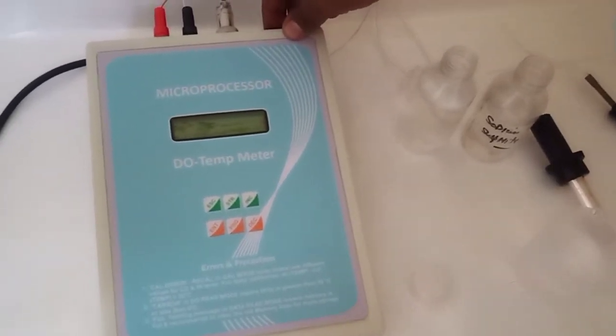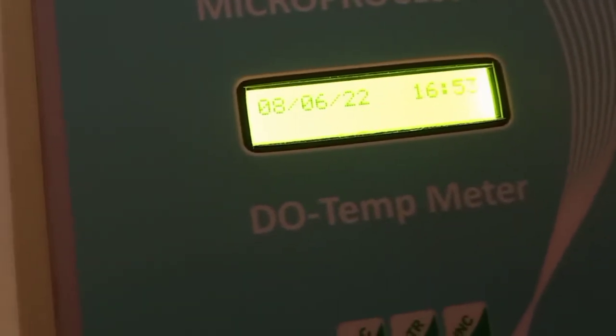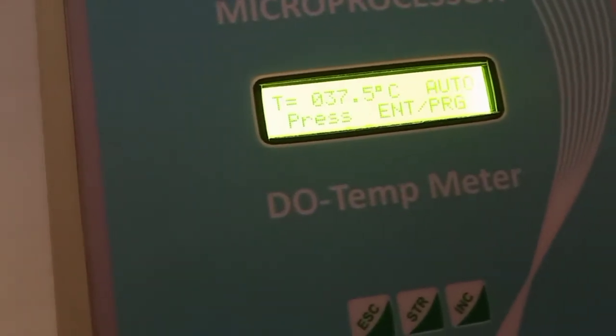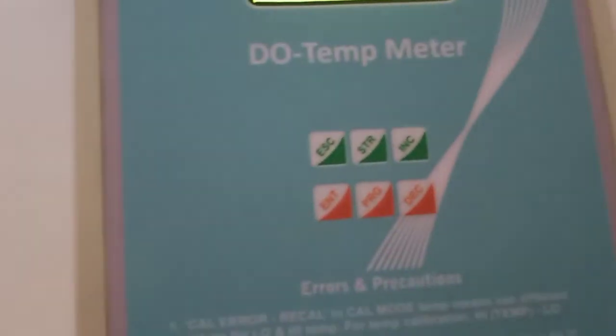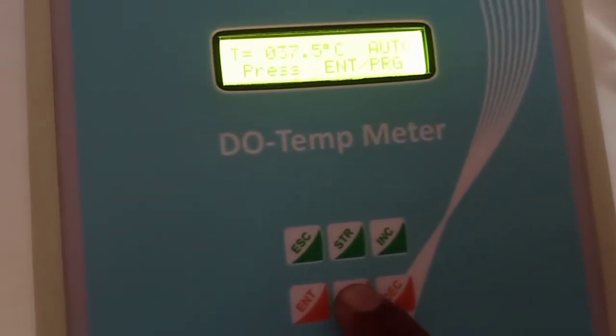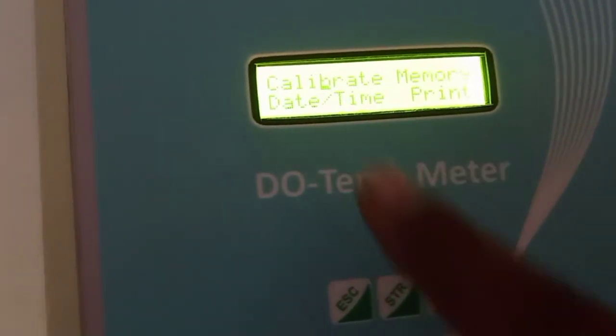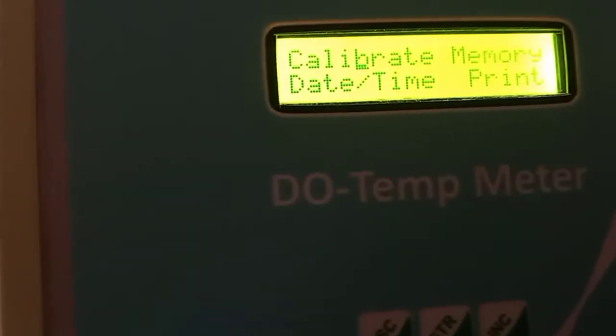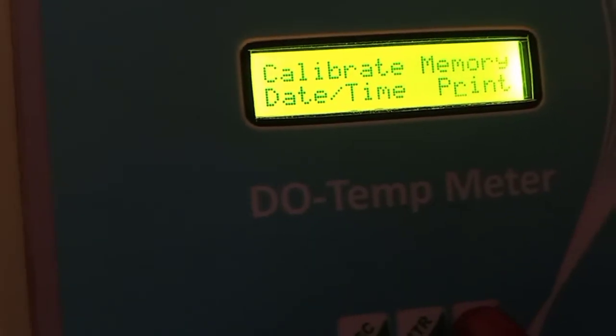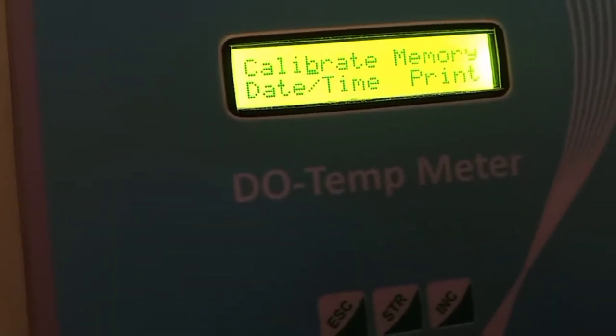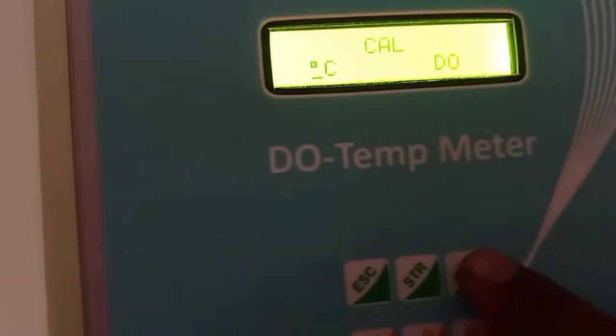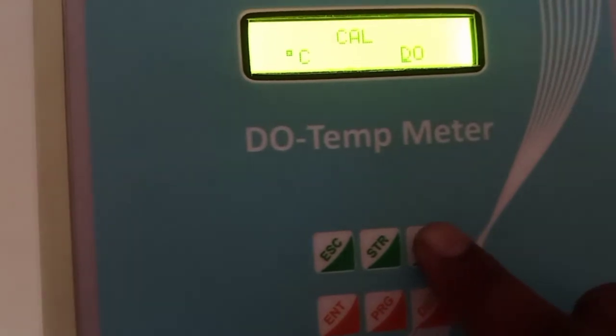Once your DO probe is ready, switch on the machine. The display shows microprocessor DO meter, date and time, and after that temperature. So for the calibration process, press the enter key, then the program key. First, calibrate. Check the cursor and move the cursor using the increment key. You can go for calibrate, memory, date and time, and print. So we want to calibrate the machine. Just move the cursor toward calibrate and press enter.